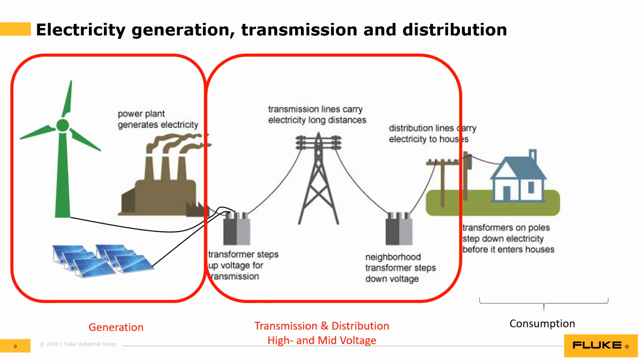Now looking into PD a little bit more, when considering partial discharge, we're talking about high voltage, so at least greater than 5 kV. From a grid network perspective, the main application is before consumption. When you talk about electrical generation, transmission, and distribution, it's usually in the generation or somewhere in transmission and distribution. So it can be the step up or step down voltage locations where it's common to have a need to detect partial discharge because they are causing issues.